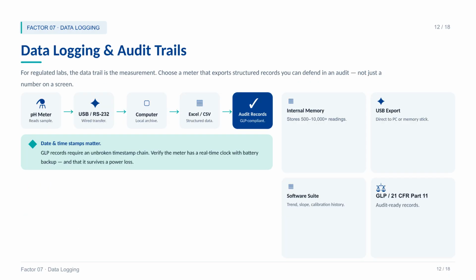Factor 7. Data logging. For regulated labs, the data trail is the measurement itself. You need internal memory, USB export, software for trend analysis, and GLP-compliant records with date and timestamps. And don't forget the timestamp. GLP requires an unbroken date and time chain on every reading. Verify the meter has a real-time clock with battery backup, so a power loss doesn't wipe out your audit trail.